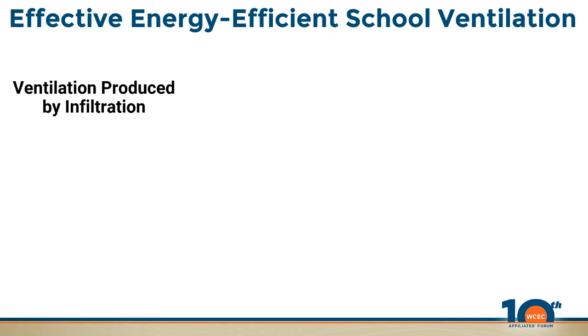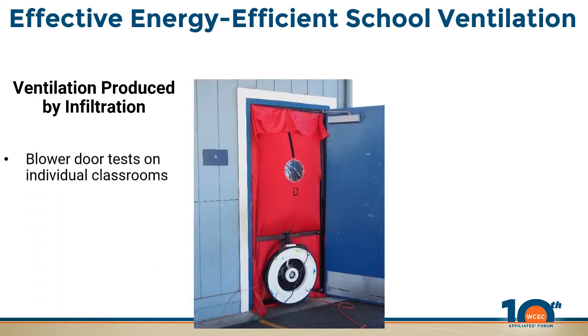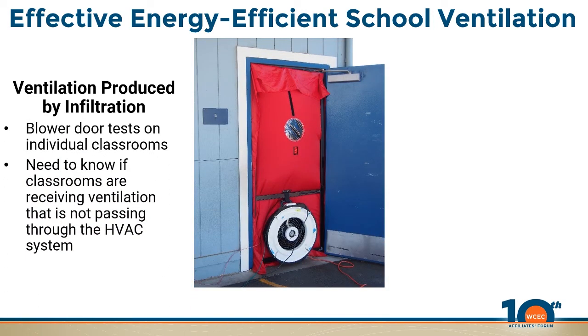Okay, thank you. In the interest of keeping with time I'm going to keep going. One quick thing: one issue we're concerned about is we're assuming all the ventilation is coming through the AC unit, which may or may not be a good assumption depending on if the room is pressurized or not. So we picked a subset and did blower door tests on individual classrooms, to figure out if classrooms are receiving ventilation that's not going through the HVAC system.